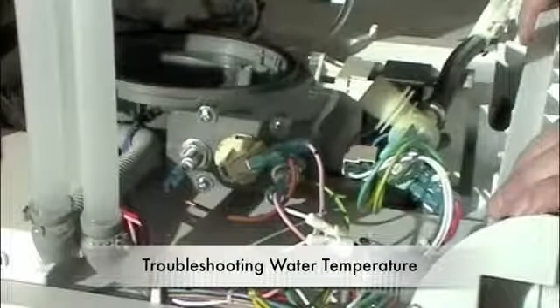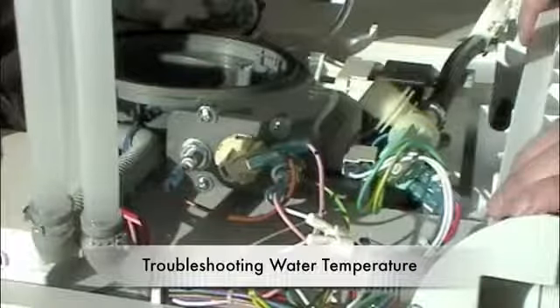Another issue that we run into sometimes is that the customer will complain that the unit is not heating the water. This does contain a small booster heater. It's right here in the center plenum assembly. Actually, you can see here at the end, and I'll move this out of the way for you, you can actually see the thermostat and the element where it actually comes out of the end of the casing.